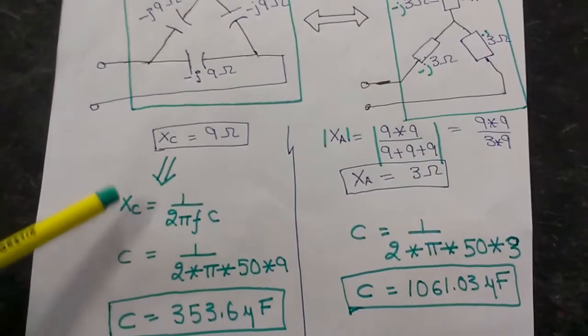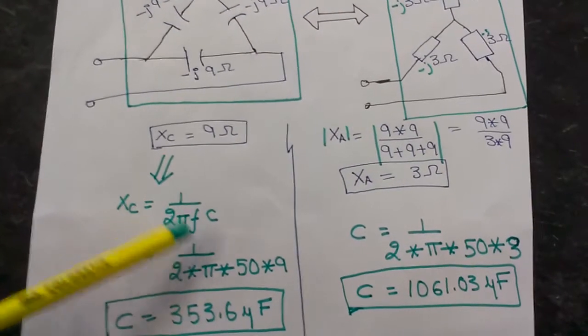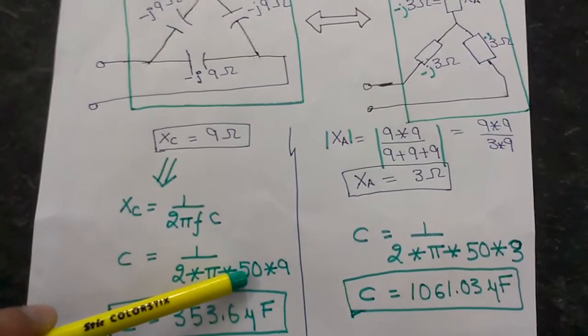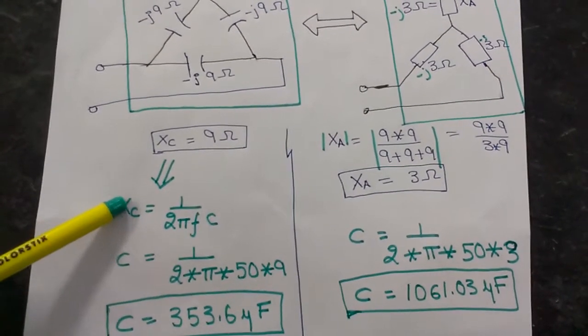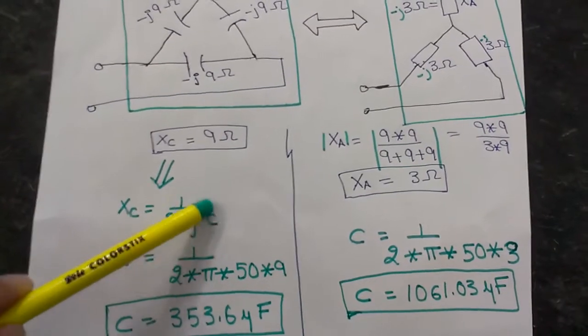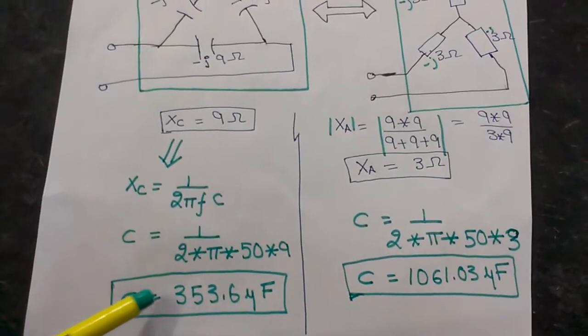And we know X equals one upon two pi FC. In India the frequency is 50 Hertz, so I have to calculate the value of the capacitor. The capacitance of the capacitor in case of Delta configuration comes out to be 353.6 microfarad.